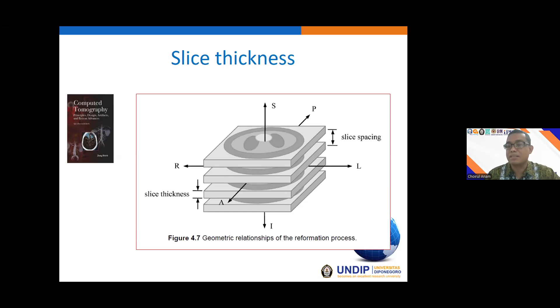Okay, this is the slice thickness and also the slice spacing. The method to obtain the slice thickness is different for single-slice CT and multi-slice CT. In single-slice CT, the slice thickness is defined depending on the beam collimation.